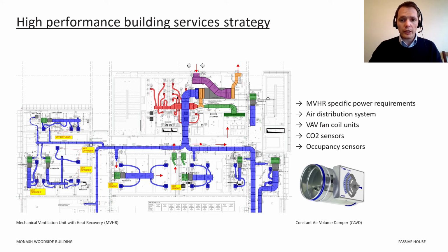The outside airflow is accurately controlled via constant air volume dampers, denoted as CAVDs. Where large quantities of outside air are delivered to a space, the dampers are motorized to modulate between minimum and maximum design values. The building management system has been set up to maintain air balancing at all times of the building operation. The fan coil units were fitted with some energy-saving initiatives, like motorized diffusers, providing variable air volume to selected spaces. These VAV diffusers have been fitted with flow meters to accurately commission the supply air flow rates through the BMS. Occupancy sensors have also been installed in various spaces to allow the fan coil units to switch off when no one is present. In large spaces, CO2 sensors have been installed to modulate the outside air requirement and subsequently reduce the fan power consumption.